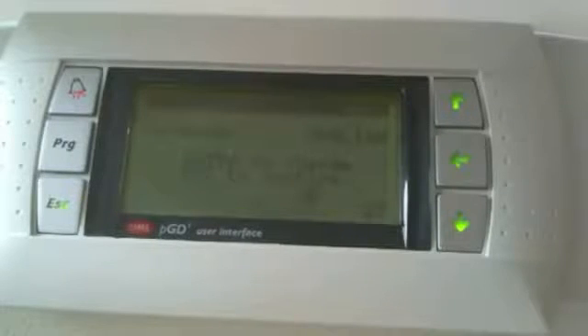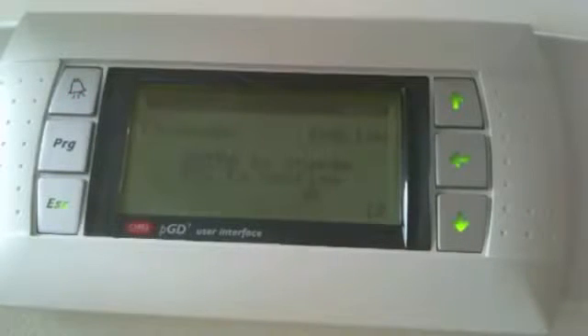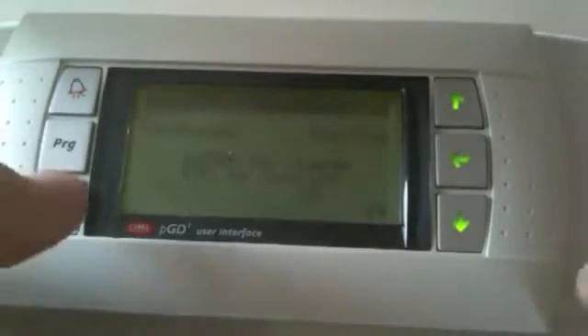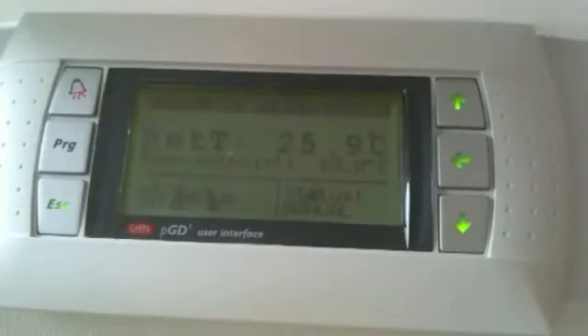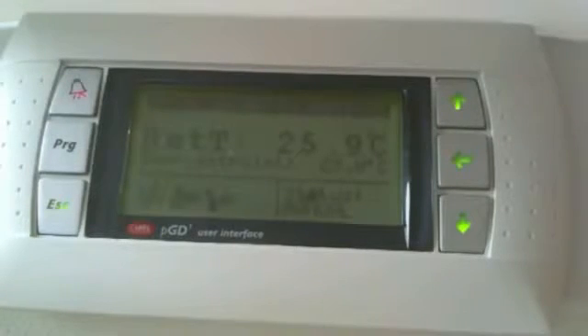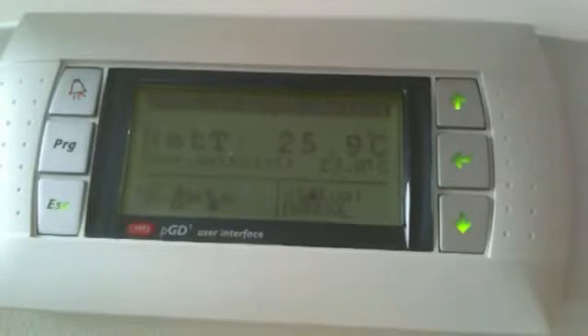We have to wait a few seconds. The 'no link' screen may appear once again, but as you can see it clears itself because it establishes communication with the controller. You will then see the main screen of the software resident inside the controller — in this case, an AHU (air handling unit) software. The PGD-1 display and the pCO3 controller are now properly communicating together.